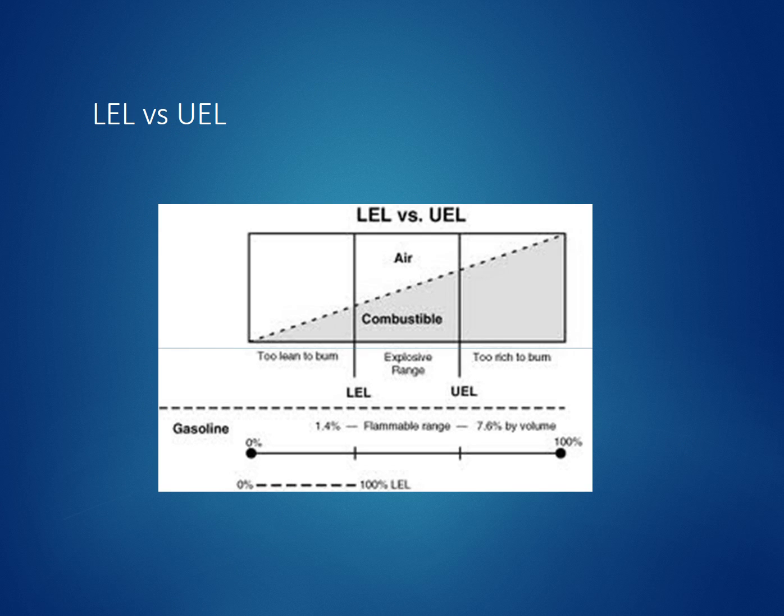Now let's look at gasoline. It has a very wide explosive range, which makes it more dangerous than a lot of different flammable liquids. This chart shows you this wide explosive range, which for gasoline is 1.4% to 7.6%. That's 14,000 parts per million to 76,000 parts per million.